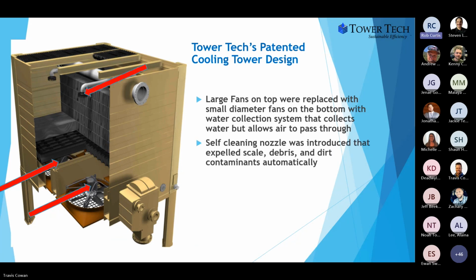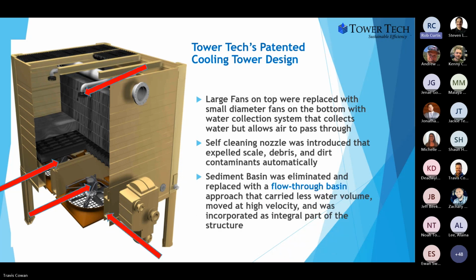The other thing that we worked on was trying to solve the cooling tower distribution issue. So obviously you got to have good water flow into the cooling tower. We developed a self-cleaning nozzle that more than just self-cleans. It's got a way that it does turbulate so that you do not plug the nozzle, but then it also has a square pattern. That's another thing that we developed. And then the third thing, it actually has variable flow capability. Those three things really have put innovation into solving some age-old problems we've seen in cooling towers.